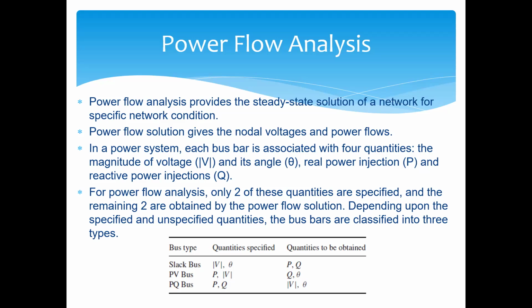Now we are going to talk about the power flow analysis tool using a distribution system model. Power flow analysis provides the steady state solution for a specific network condition. The steady state solution is given by load flow analysis. Power flow solution gives the nodal voltages and power flows. We can obtain nodal voltage and power flows using power flow analysis. In a power system, each bus bar is associated with four quantities: the magnitude of voltage and its angle, real power injection, and reactive power injection. For each bus bar, we have voltage magnitude and voltage angle, and real power consumption and reactive power consumption.